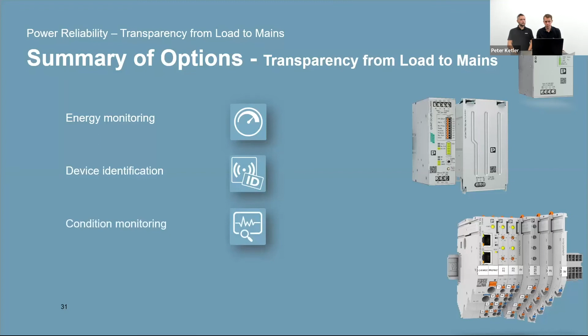Also, as I explained, you can configure the power supply via the PLC, centralizing the configuration and reducing failures, since it's done automatically. This also helps reduce failures on remote applications, like on ships, where you're not fully confident there's somebody able to configure the power supply the way you like. You just plug it to the PLC, and the power supply will be automatically configured, as well as the circuit breaker.